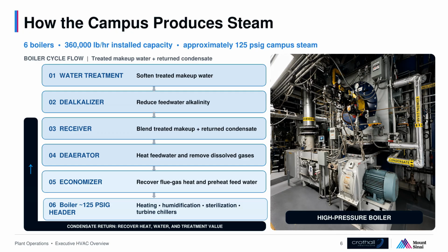The boiler plant adds heat to water and distributes that energy as steam. Start with make-up water treatment. The softeners remove hardness that could form scale on boiler heat transfer surfaces. The dealkalizer reduces feed water alkalinity. Treated make-up water then combines with returned condensate in the receiver. From there, the deaerator heats the feed water and removes dissolved gases, especially oxygen, that contribute to corrosion. Feed water pumps move the water toward the boilers, and the economizer recovers heat from the flue gas to preheat that water before it enters the boiler.